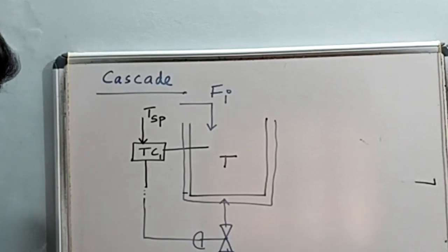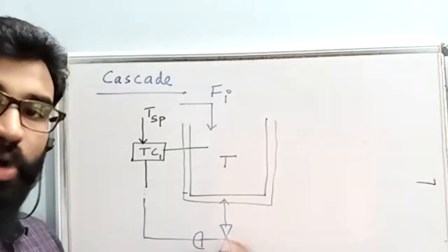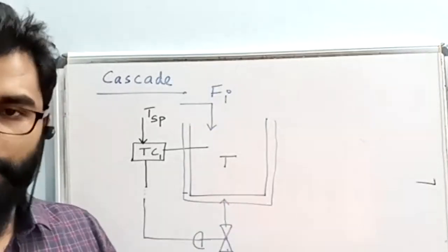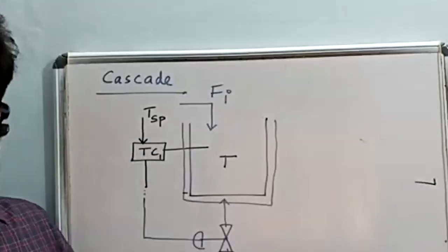Exothermic reaction coolant. Which valve will we select? Air to close or air to open? Fail open, correct? Fail open means air to close, right? So all the answers are correct. If the valve fails, it should open and coolant should flow in, so we avoid whatever injury or damage. So this is the point.